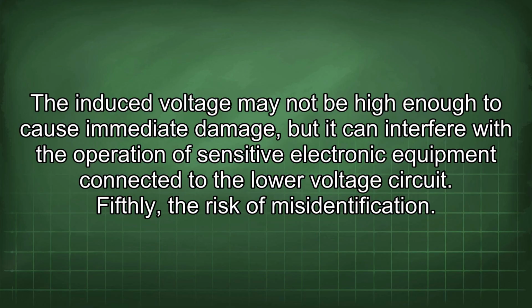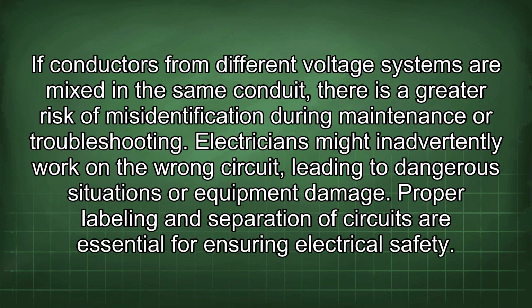Fifthly, the risk of misidentification. If conductors from different voltage systems are mixed in the same conduit, there is a greater risk of misidentification during maintenance or troubleshooting. Electricians might inadvertently work on the wrong circuit, leading to dangerous situations or equipment damage. Proper labeling and separation of circuits are essential for ensuring electrical safety.